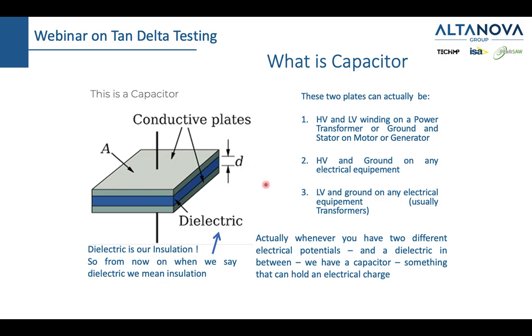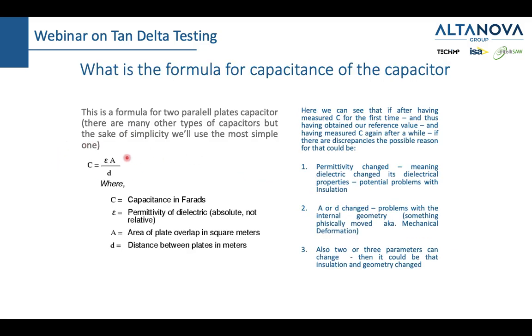But in order to do that, we need to dig a little bit deeper. We need to see the basic formula for a two-plate capacitor. So we can see here that we have a capacitance, a permittivity, the area, and the distance. The bigger the area, the bigger the permittivity, and the smaller the distance between the plates, the more electrons I can store inside. And this is the core of understanding tan delta, because first of all, the permittivity is one thing which can change, and it can change if, for example, the properties of our insulation change. If our oil gets too many water molecules inside, the epsilon will change. Also, if there was an earthquake, heaven forbid, and the two plates or two windings have become closer, then these two parameters will change.